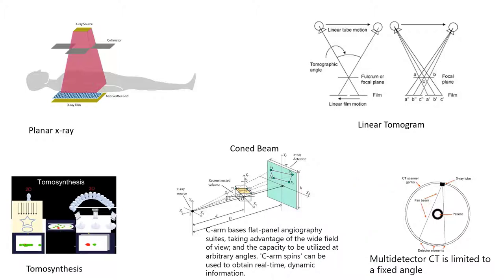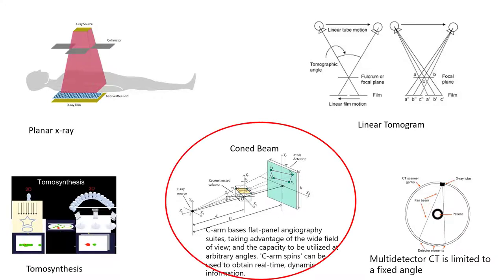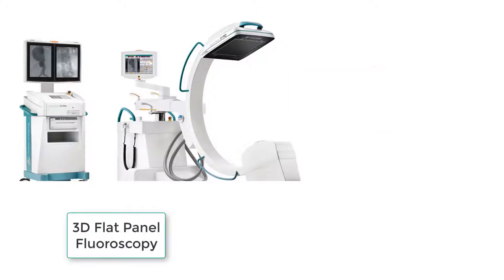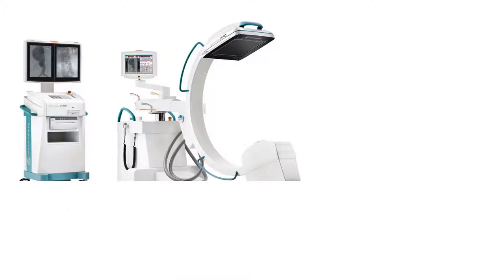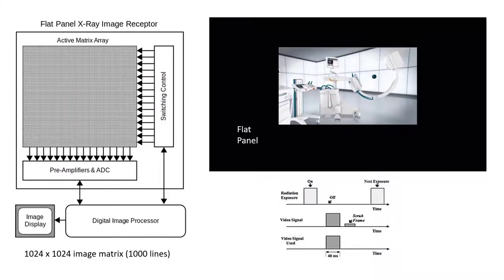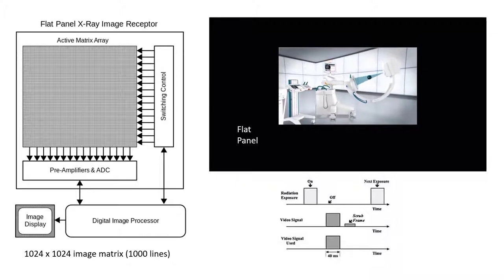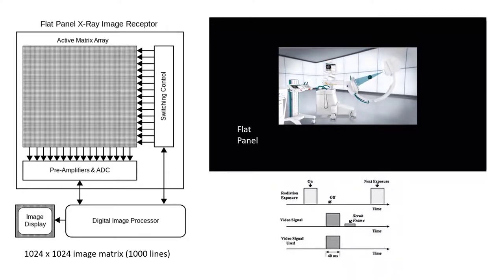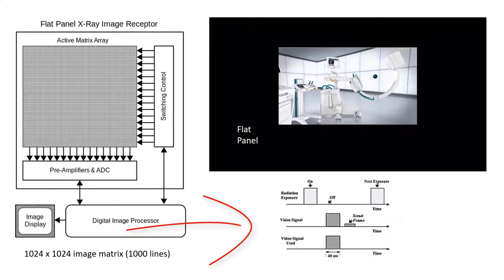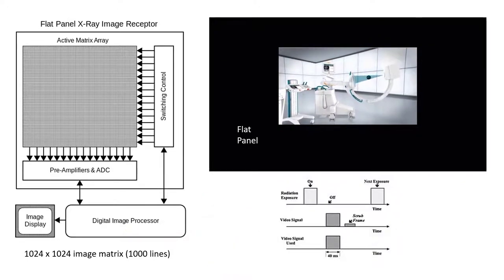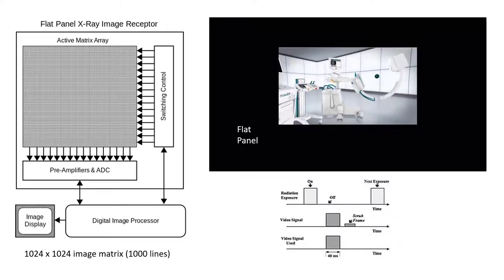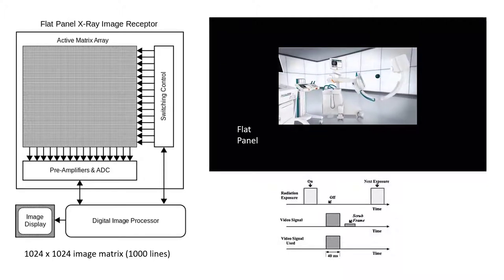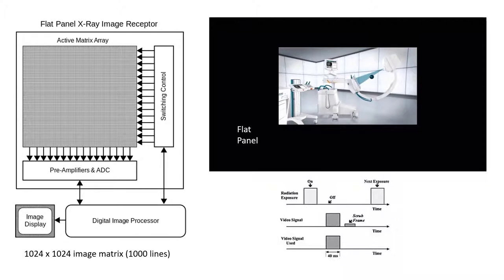Cone beam CT refers to any modality that uses a wide-angle field of view. The fluoroscopic cone beam CT scanner uses a flat panel image receptor and digital pulsed fluoroscopy to create images. The flat panel enables high resolution images while pulsed digital fluoroscopy reduces patient exposure. Three-dimensional fluoroscopy units with cone beam CT acquire images at less than 360 degrees in one rotation.